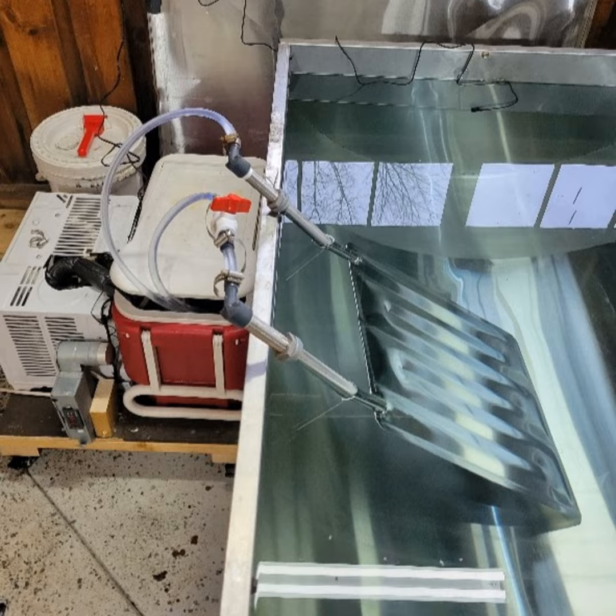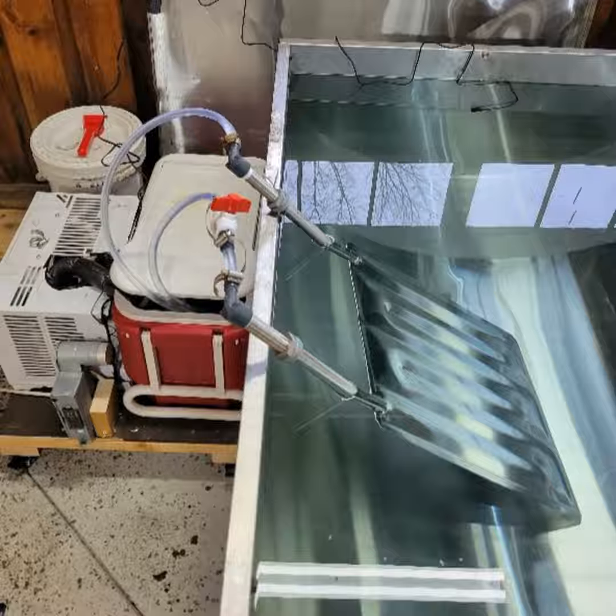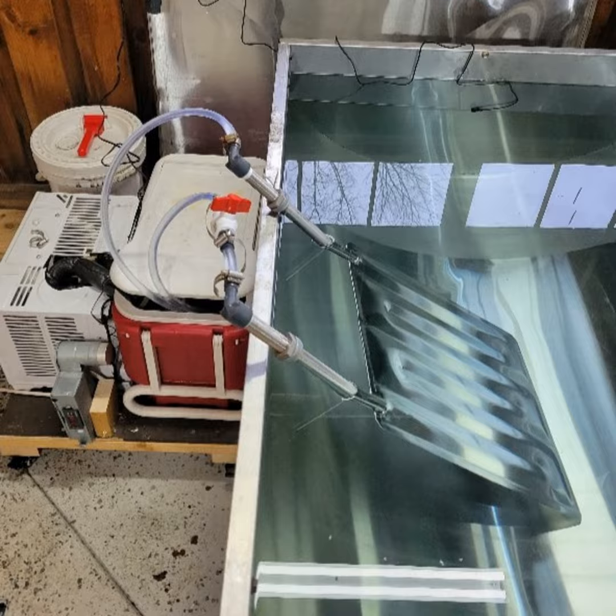So we didn't think we needed both sets of plates. We hooked it up with one set of chiller plates and the compressor, and we spent $7,500 on the tank and the compressor. Then we had to hire a contractor to hook it up and pressure test it and make sure everything was good. We hired a local dairy company, and that cost another $4,500, which was a lot more than I expected, but everything worked.